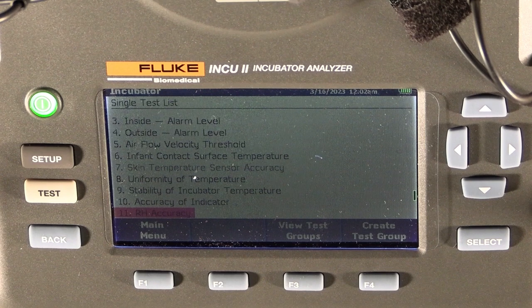Number 11 is our relative humidity accuracy. Not all incubators are equipped with humidity, but for those that are, you'll follow the guidelines in your user manual, filling up the water in your unit and setting your humidity. Again, we'll wait for the unit to reach a stable temperature, and then over a period of time we compare the humidity reading from the FLUKE unit to the humidity reading of your incubator.